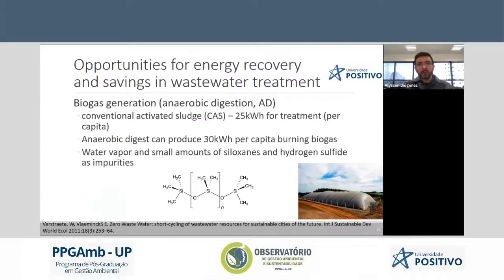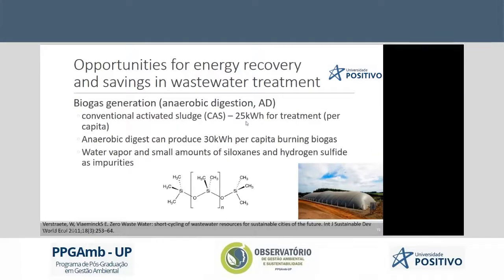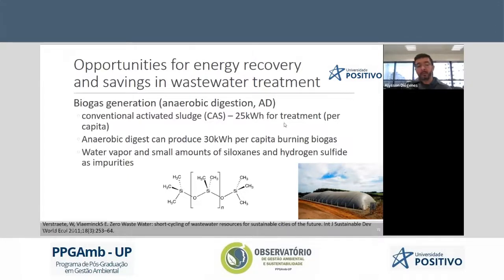Another opportunity for energy recovery and saving in water treatment is biogas production through anaerobic digestion. Using conventional activated sludge costs 25 kilowatt-hours per capita, and each person generates this. The anaerobic digester can produce 30 kilowatt-hours per person, so we can have a 5 kilowatt-hour profit from energy generation.